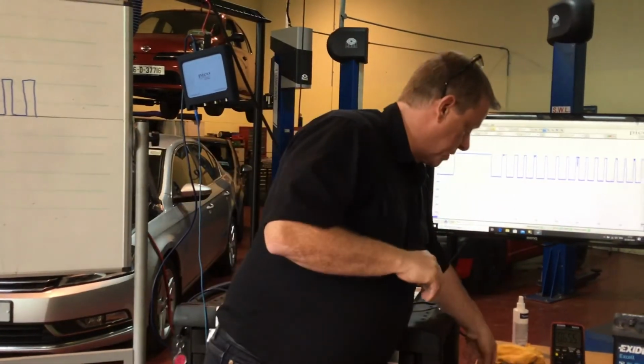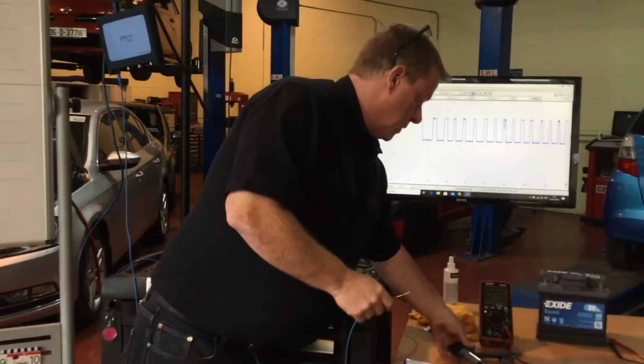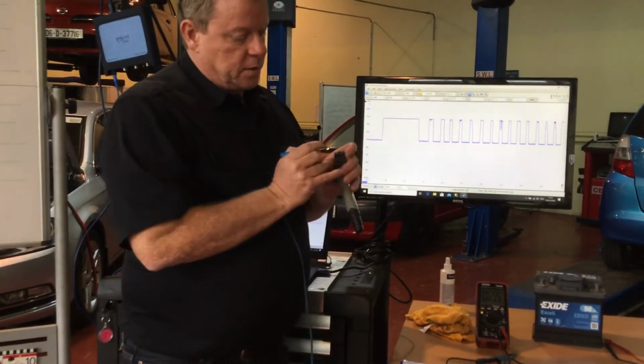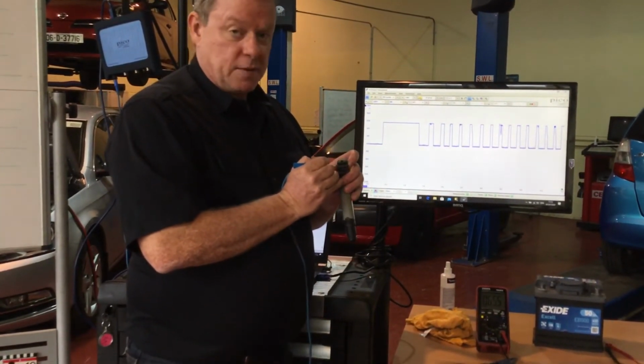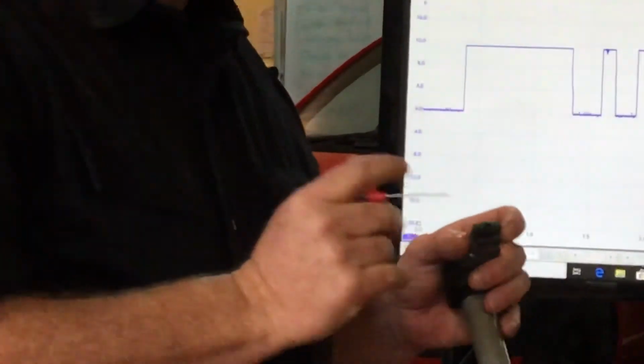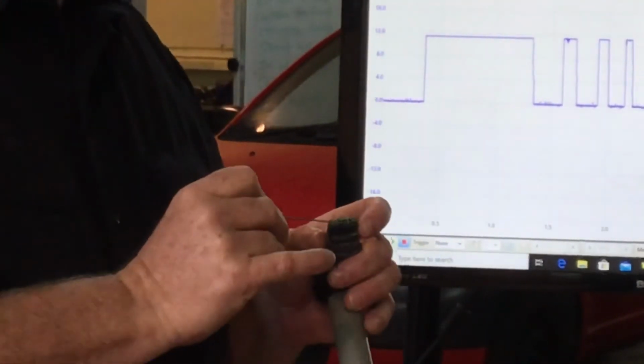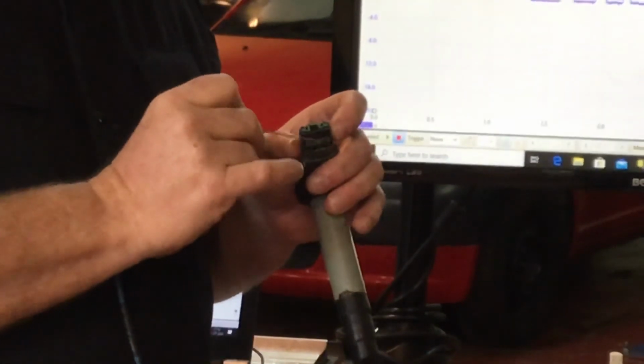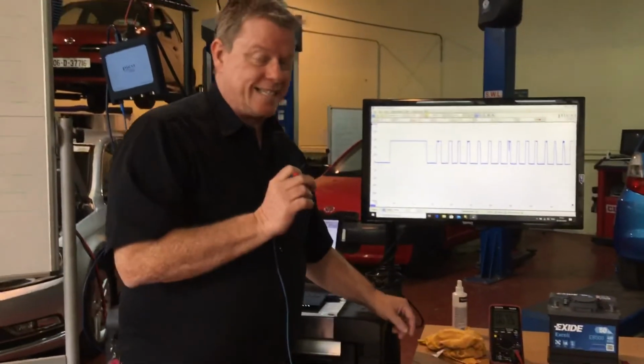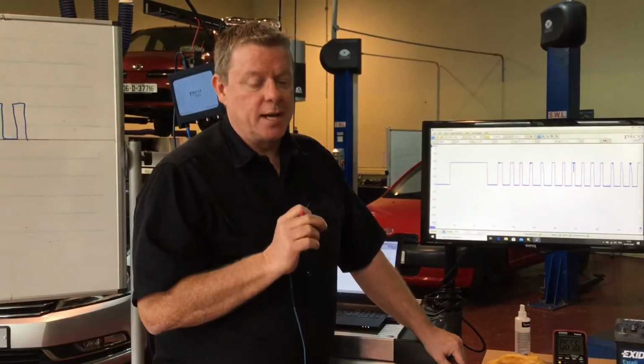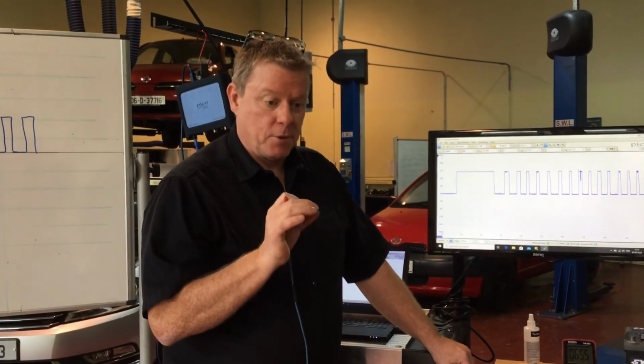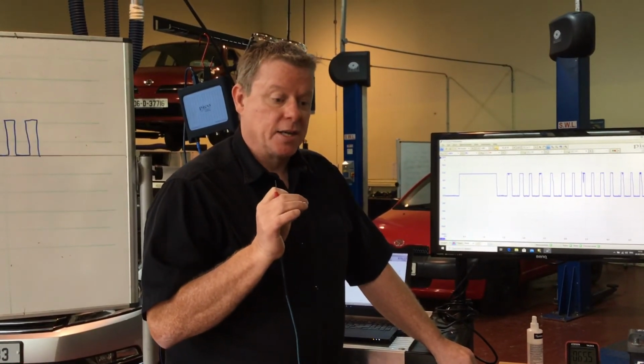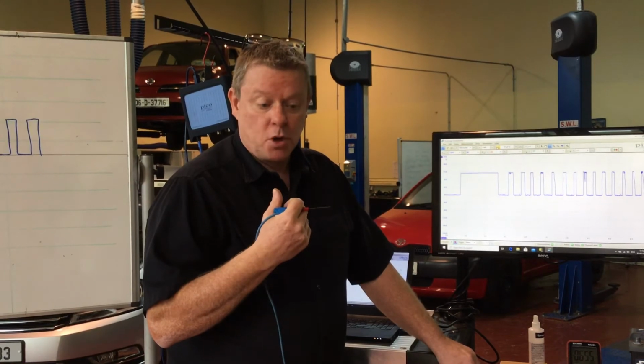While we're on the topic, you sometimes see people stabbing into the actual wire itself to get a signal off it, which is fine in some cases. But if you probe into a wire, you break the insulation. In some cases you will have to do that, but what you have to do is seal it again, because you can put a hole in and allow moisture to get in there and cause corrosion inside the wire itself if it's left unsealed.